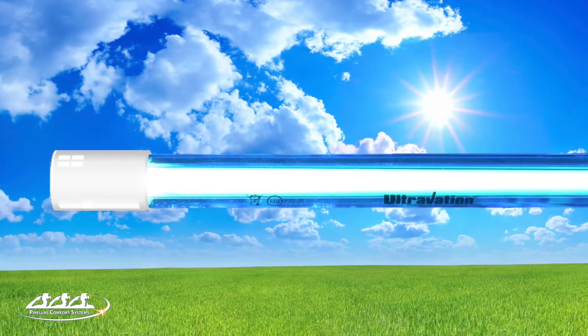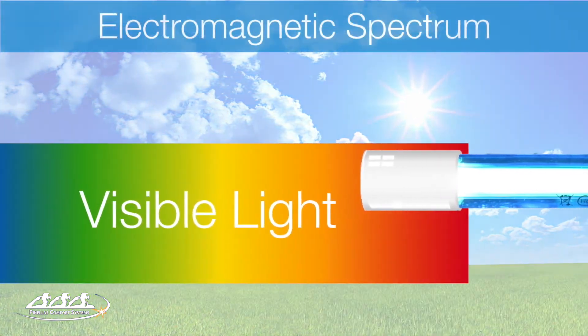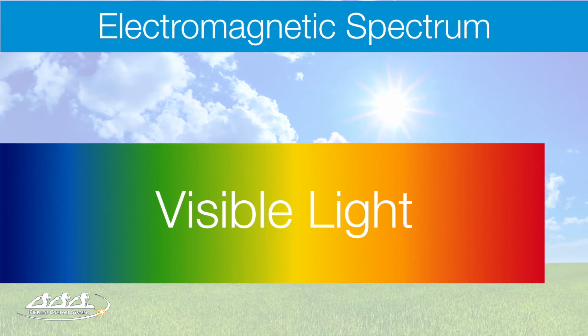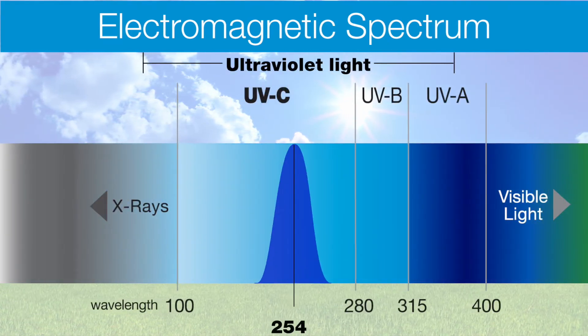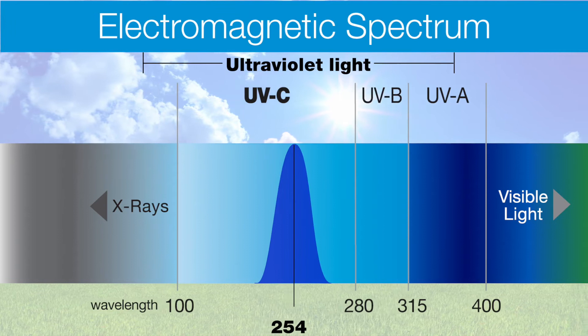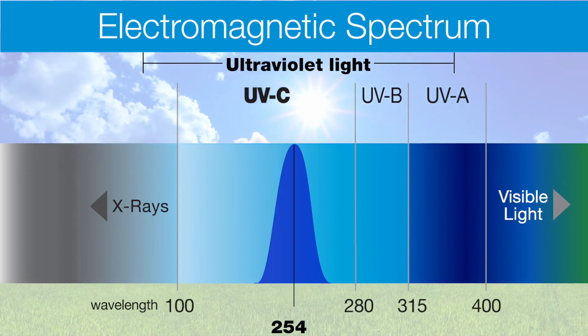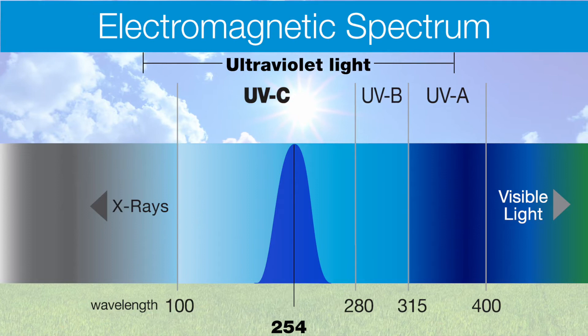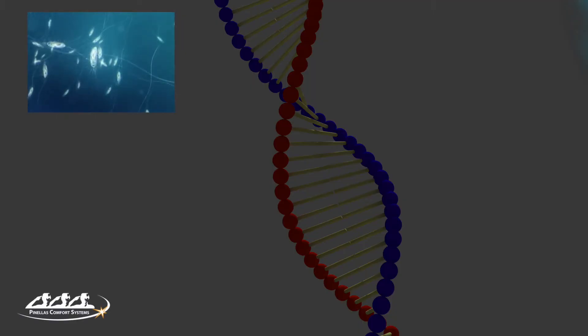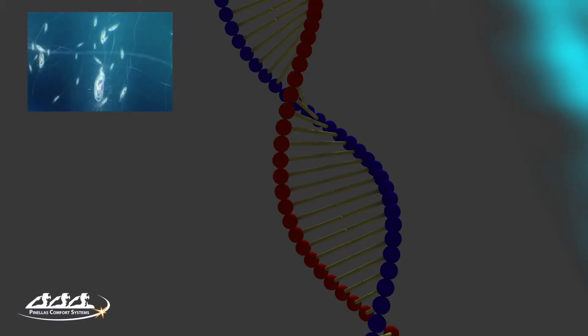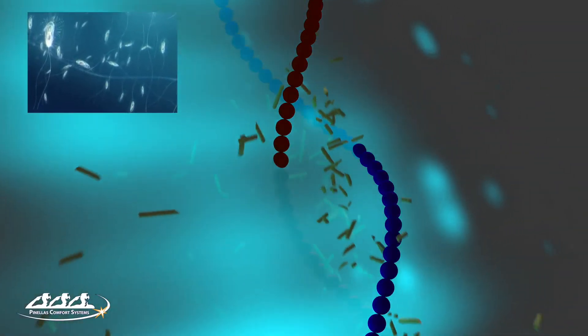UV light is a natural disinfectant and a component of sunlight. Scientifically, UV is a part of the electromagnetic light spectrum falling just below the visible light frequencies, and the germicidal wavelength of UV light centers on 254 nm. UV light works as a disinfectant because it is able to penetrate cell tissue and break up cellular DNA.